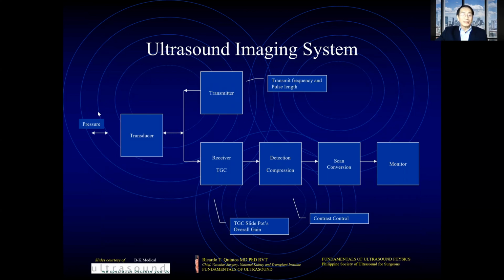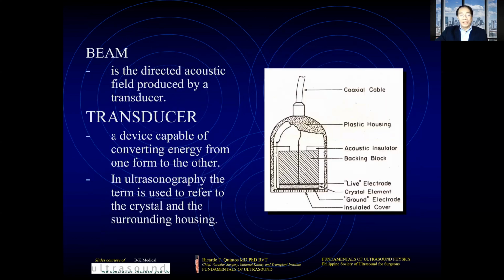So we talked about the pressure, and now we will be talking about the transducer, whose job is to produce the ultrasound so that it will be transmitted to the organ of interest. And then it also picks up the echoes of the sound so that they will be analyzed by the CPU. The analysis of the CPU will then move the data to the monitor for visualization. So basic transducer theory is that the transducer produces a beam which directs the acoustic energy produced by a transducer.